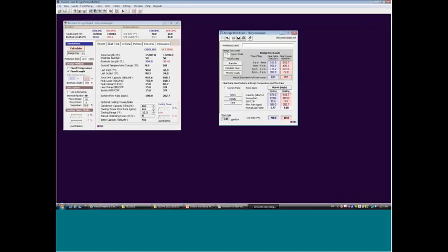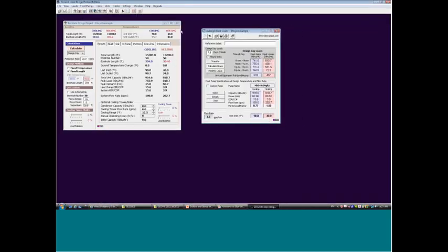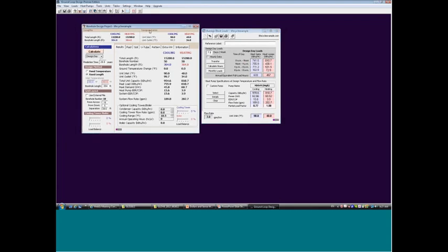So I have the program, the Ground Loop Design 2012 program here, and I've done a preparatory loop field design. I'm just going to walk you through it very briefly so that we're all on the same page. So I imported an hourly loads profile for approximately a 40,000 square foot building. See my cooling peak loads here around 60 ton. My heating peaks are a little bit higher. My annual energy is around here, or my annual hours.